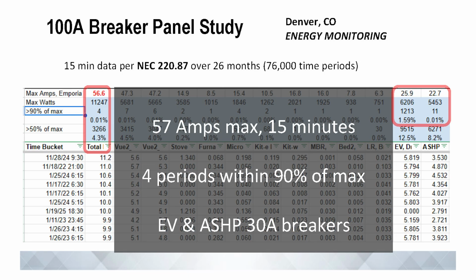This is my house — an all-electric house with the car and everything — and I have a 100 amp panel. Running my whole house on a 100 amp panel should be illegal according to NEC, apparently. But not really, because there's a clause in NEC that says if you gather 15-minute interval data for a month and demonstrate you have the capacity on your panel, you're good to go. It's called an existing load study. They ask for 15-minute data over a year in the code section, but there's an exemption allowing just 30 days of it. I did it for over 2 years.